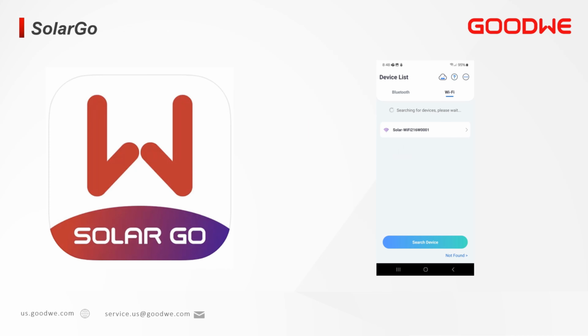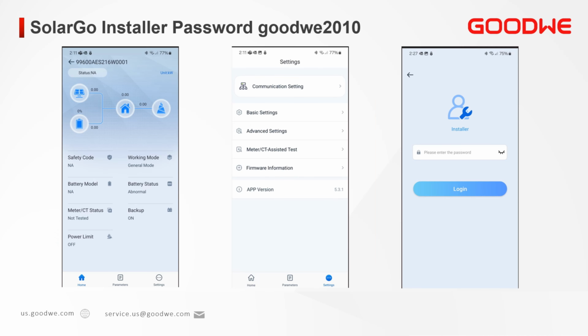Now open SolarGo. It will first search for the nearby device. This could take a few seconds. Then the inverter should appear with a Wi-Fi connection. Click on the Solar Wi-Fi and the inverter serial number. From the main screen, click on the bottom right settings, select Basic Settings, and enter the installer password as you see on the screen, GoodWe 2010.